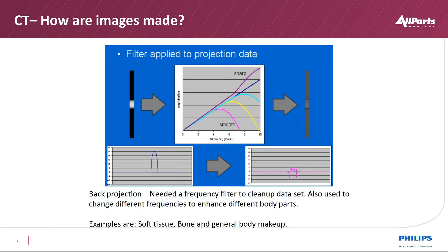So we'd use a different frequency response filter. Luckily, what we do is take the raw data set that we scan the patient with. We save that as what we call raw data or scan data. Then we can apply this filter and create an image set with soft. Then we can take the same data set, apply a sharp filter, and then we have two DICOM images from the same DICOM, not DICOM, but raw data source. So we can take that data and manipulate it in many ways to enhance what we're trying to achieve by looking at what happens with the patient's anatomy.